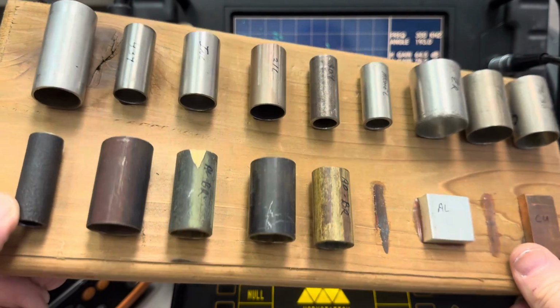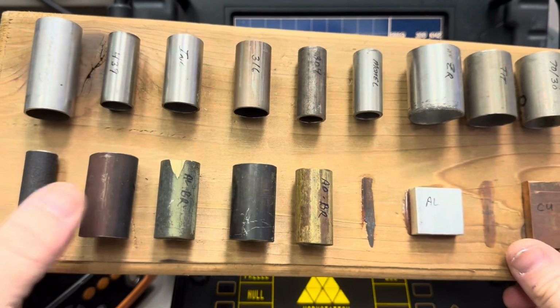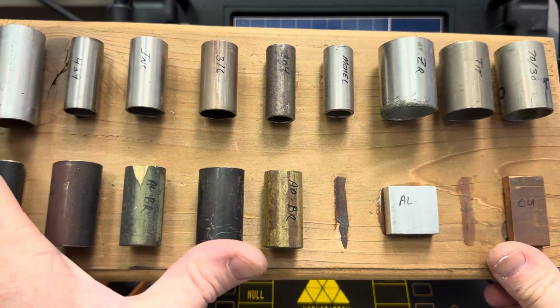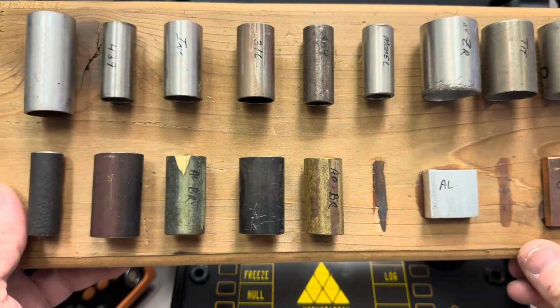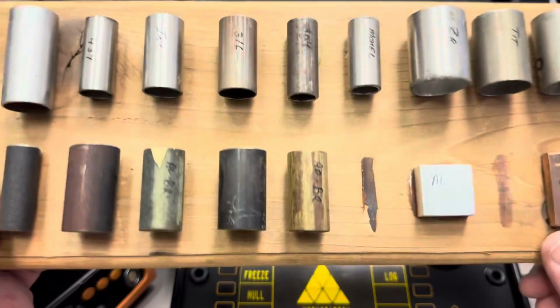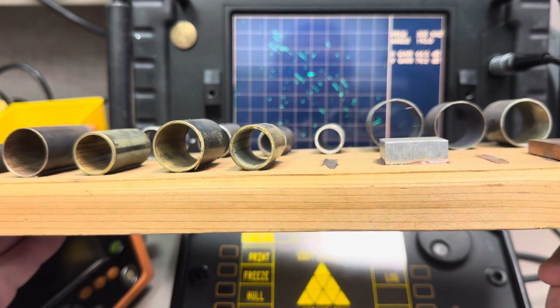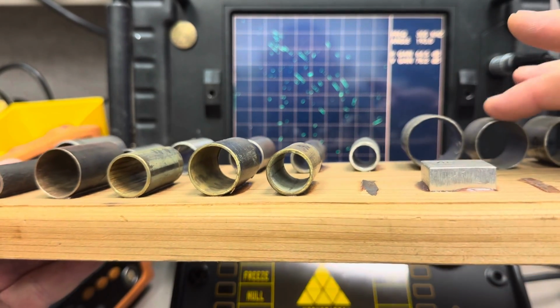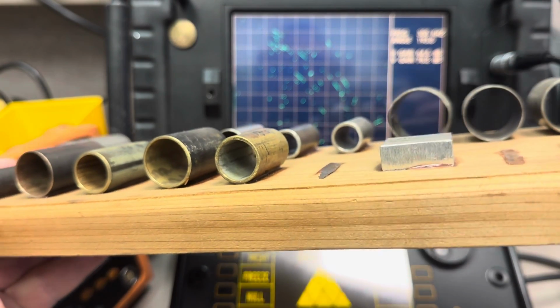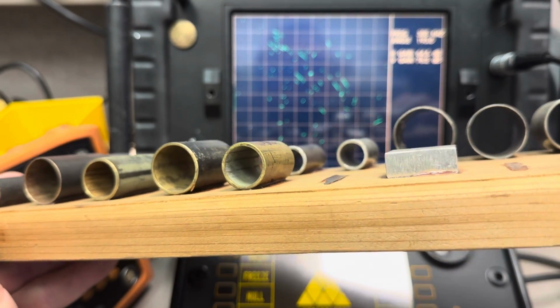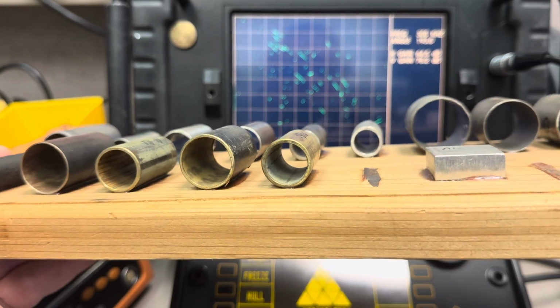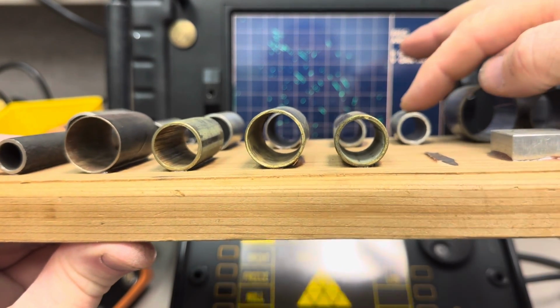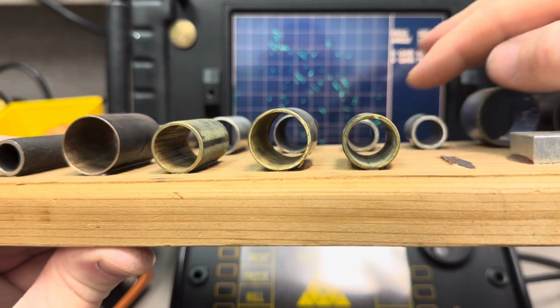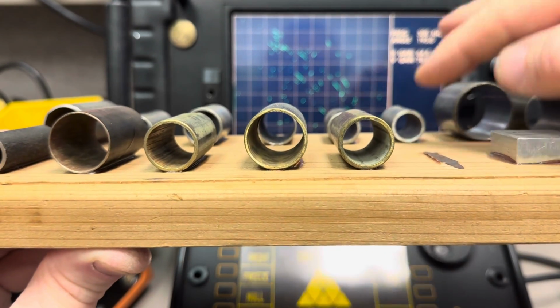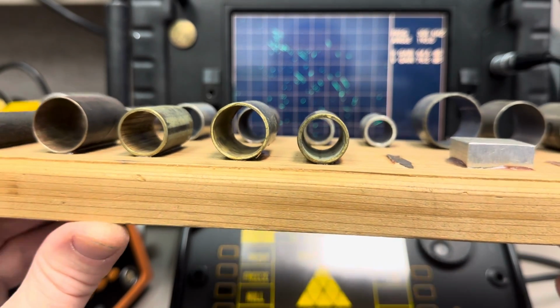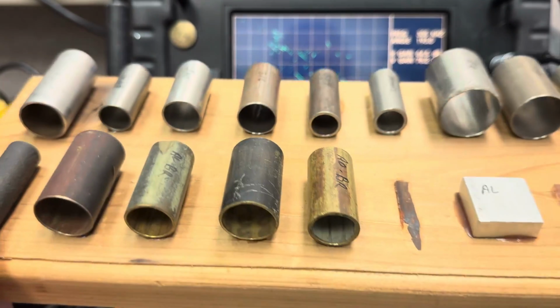Then you got something that's dark. I can't read that one or that one. This is aluminum brass, Admiralty brass. Now, what's interesting is you look at these tubes, look at the titanium over here. Look at how thin that wall is, because titanium's strong, right? That's why they put it on fighter jets. And then in contrast, look at some of these smaller tubes. Look how thick the wall is there. So obviously, if you have thicker tubing, you probably need lower frequencies to penetrate through the tube wall.